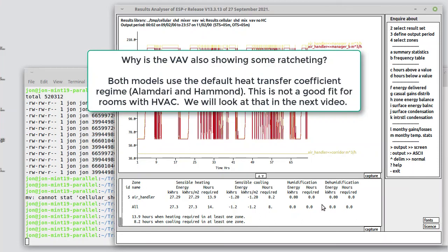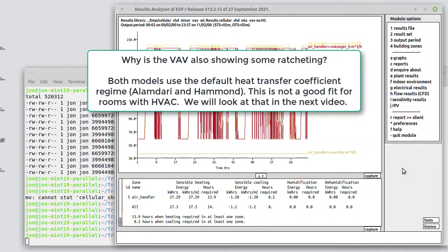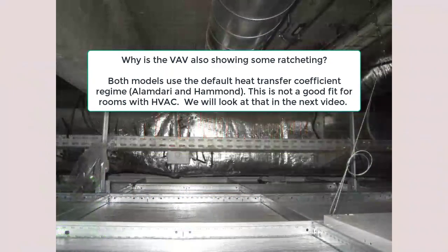So why do we see some ratcheting? Well, both the models use the default heat transfer coefficient regime, Alamdari and Hammond, and that's not really a good fit for rooms with HVAC. We will look at that in the next video.